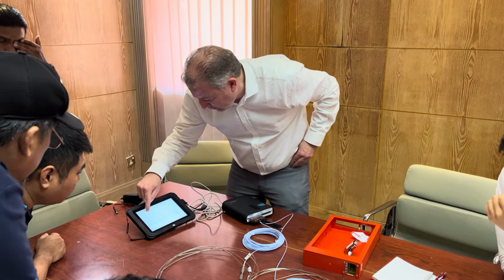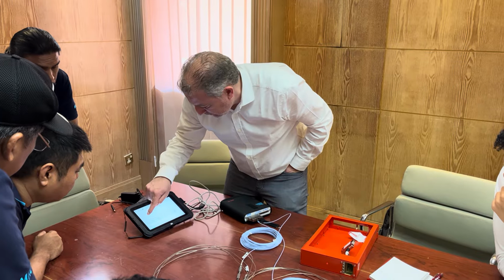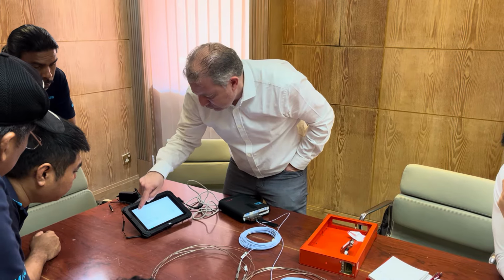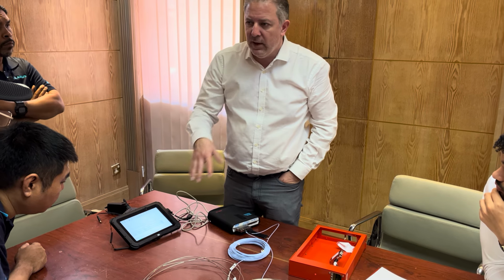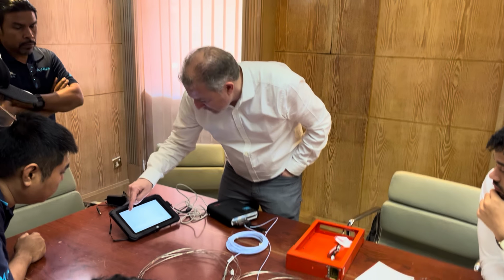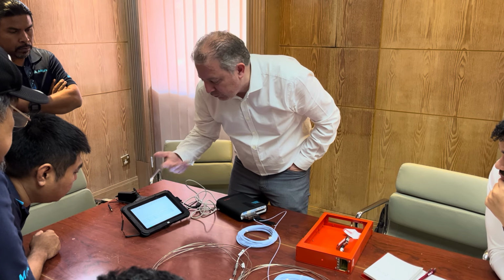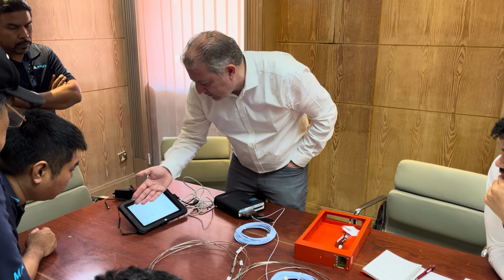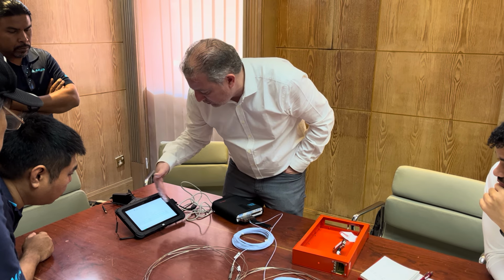So you see two graphs. You see a green graph behind. Green is the golden reference that was taken for that bench, and blue is the current measurement. Okay, so I can use this expert mode to analysis. So now I see it matches very well.